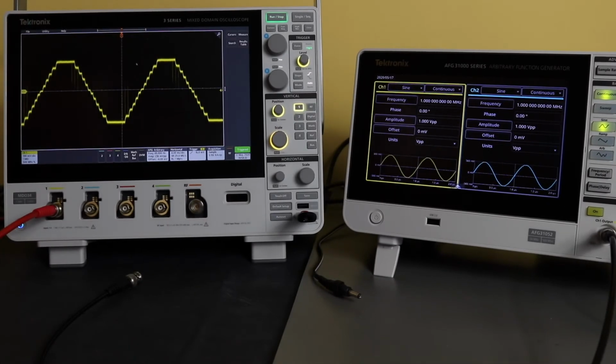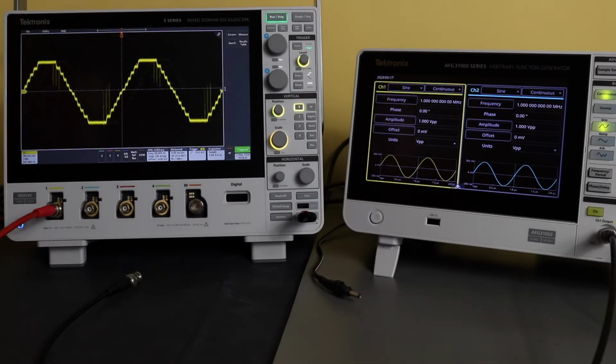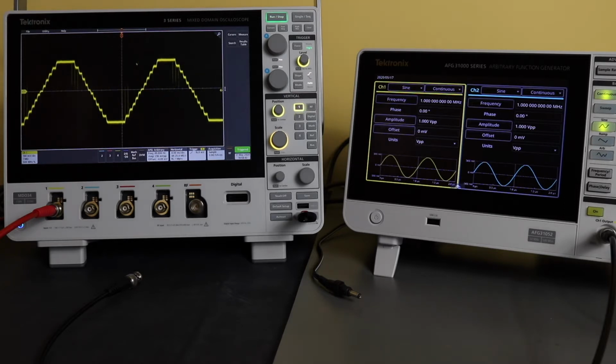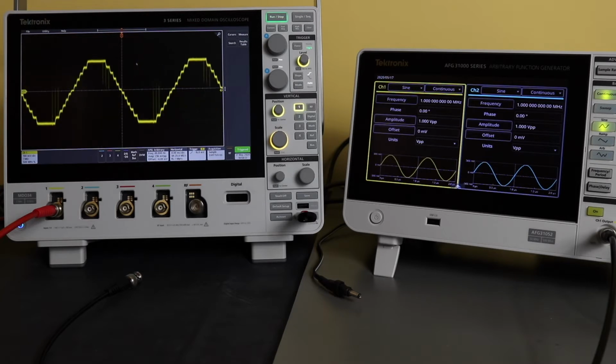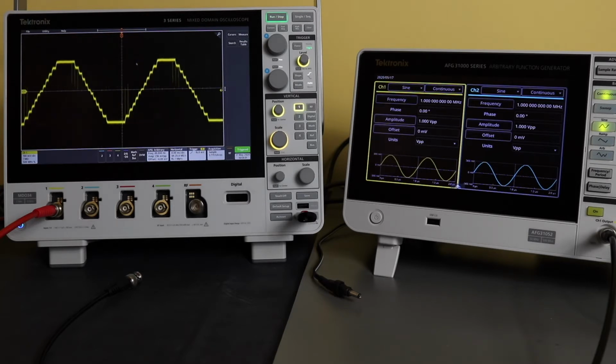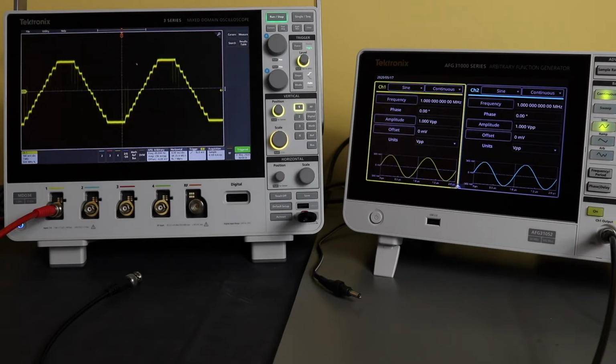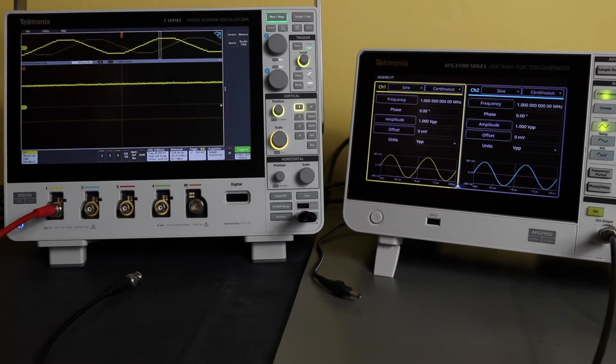This next video on the AFG 31052 is about creating test pulses for verification of partial discharge test apparatus. On the left here on the oscilloscope I've got a test pattern that has been captured from some test apparatus, and you can see it's made up of two elements. The first element that's immediately obvious is the stepped 50 Hz sine wave, but along that sine wave there are small sections of pulses being displayed, which I can hopefully show you.